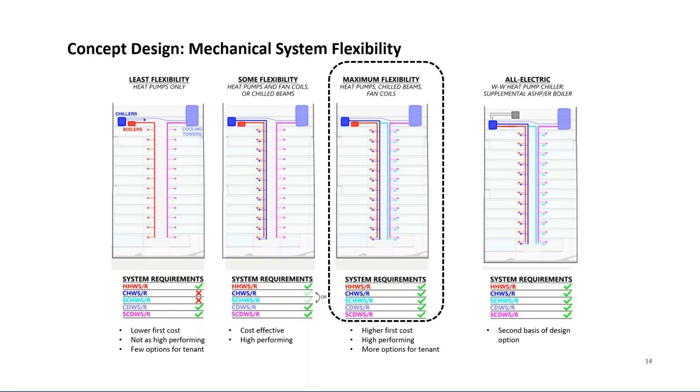And then we also have a condenser water loop that we generally will send down through the building, sometimes for mission critical loads, whether it's IT rooms or things like that, and sometimes for retail tenants, who will be provided with stub outs into their space, and they have to use condenser water and heat pumps to deal with their space, a lot of times at the podium of these buildings. But then we'll have a secondary riser ideally, and certainly in all of the chilled beam designs that we do, we'll have a riser that has the 57 to 58 degree chilled water supply temperature. And we found that having this level of flexibility, especially in the higher end Class A office and lab spaces, is desired.